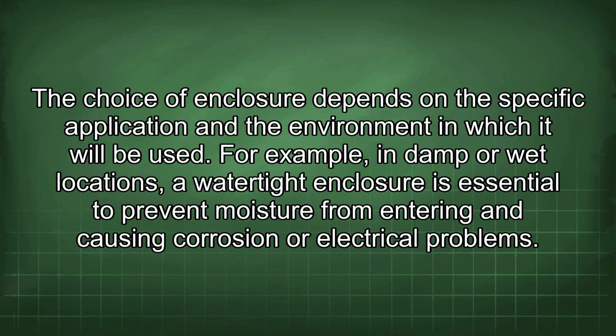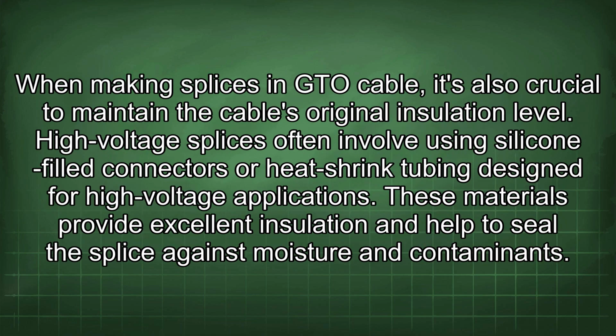The choice of enclosure depends on the specific application and the environment in which it will be used. For example, in damp or wet locations, a watertight enclosure is essential to prevent moisture from entering and causing corrosion or electrical problems. When making splices in GTO cable, it's also crucial to maintain the cable's original insulation level. High voltage splices often involve using silicone-filled connectors or heat shrink tubing designed for high voltage applications. These materials provide excellent insulation and help to seal the splice against moisture and contaminants.